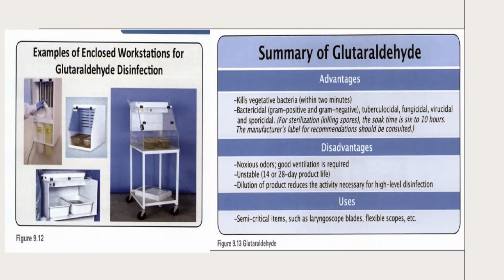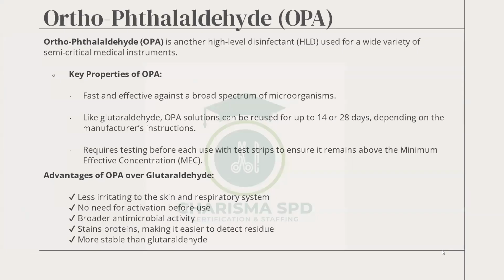Okay. Yeah. Now, soak time is relative. It can also apply to the decontamination room. I want to clarify that. That's why I said it is relative, depending on where it is used. But here we are on high-level disinfection, so it applies to the time the instrument will stay in the chemical for the disinfection, for high-level disinfection, or the sterilization, which is the 10 hours. But we can also use soak time for decontamination, where an instrument has a specific time it must stay in the enzymatic detergent in the decontamination. So soak time can be used for the decontamination area, depending on what you are talking about. I believe I've explained this to your understanding. Yes. Correct. Thank you. All right, next slide, director, please.